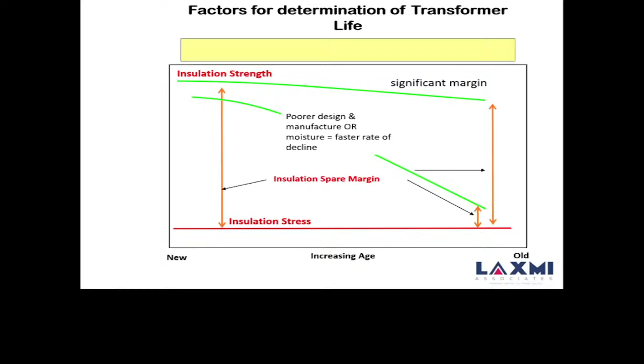So what you are seeing is that if a transformer is designed well and there is no stress, it can age very nicely, having a good strength, that means the DP value will be very good. But because you have different constraints, system transients, short circuit forces, thermal stress, mechanical stress in terms of fault, and moisture as a dielectric aging parameter, all those things reduce the withstand capacity of the insulation, and that is how you reach the end of life. And we define that there is a life of 30 years, 50 years, whatever, depending on the application, whether there is a generator or it's a transmission unit or an industrial unit, we define the residual life of a transformer.